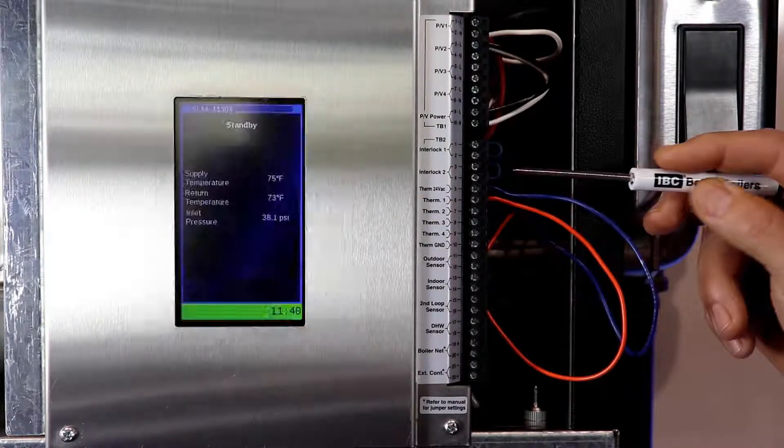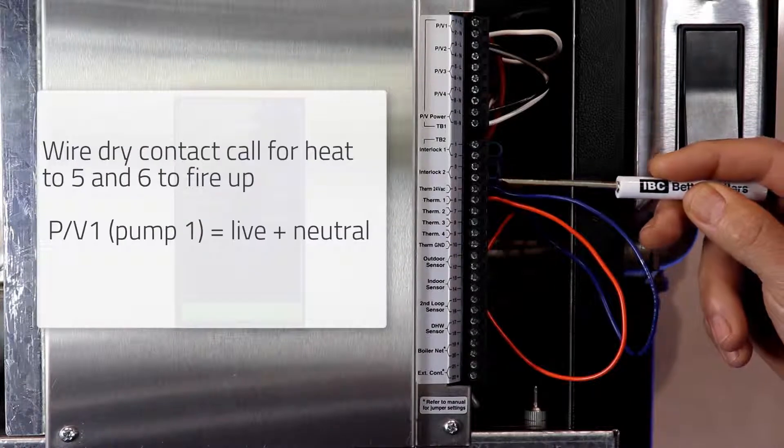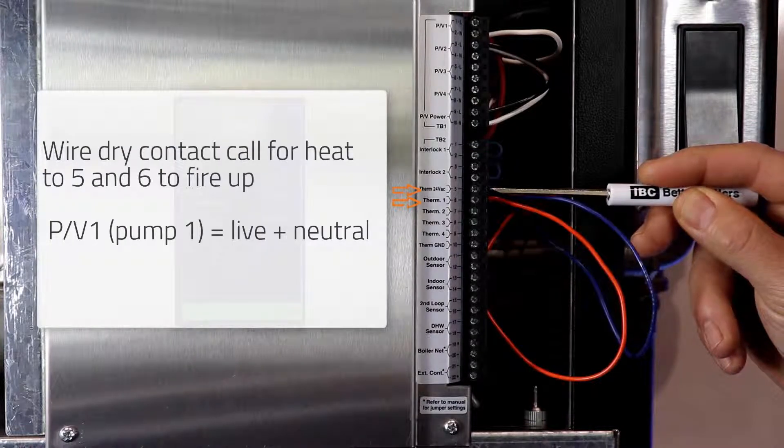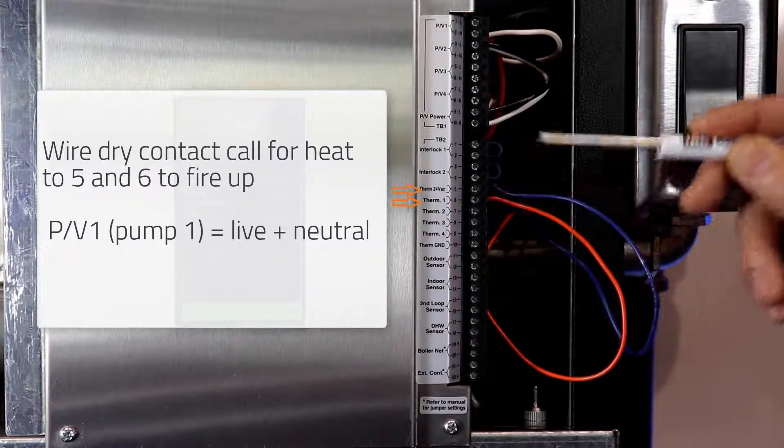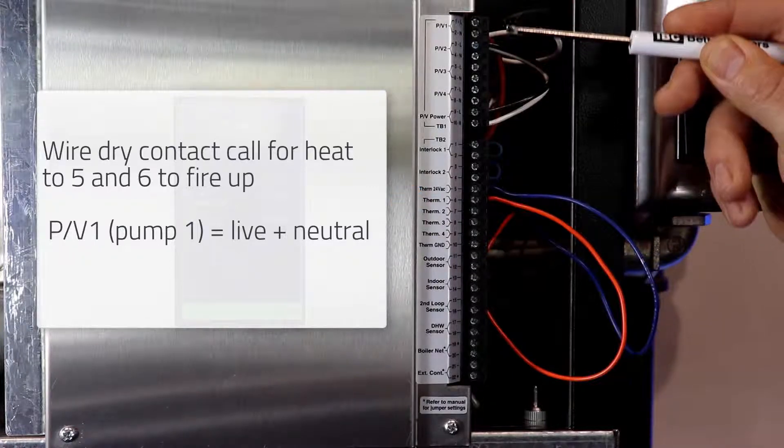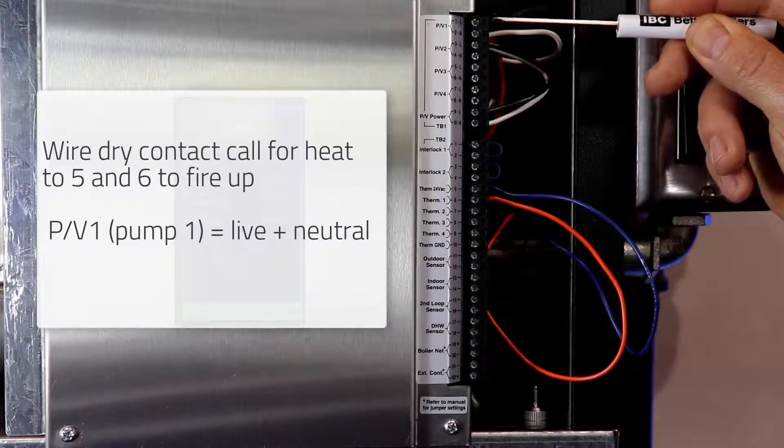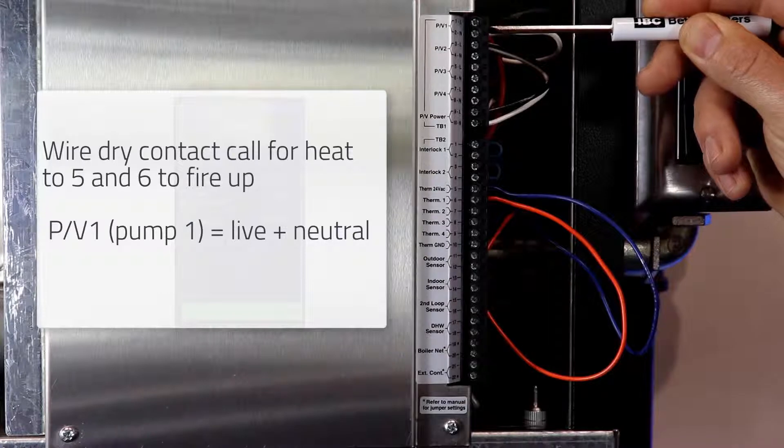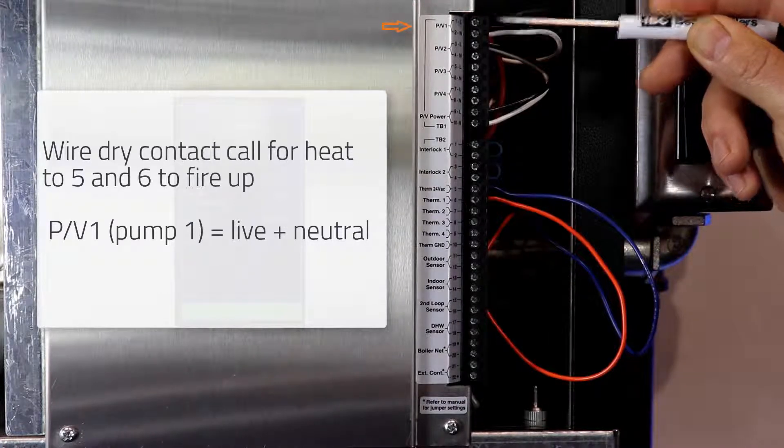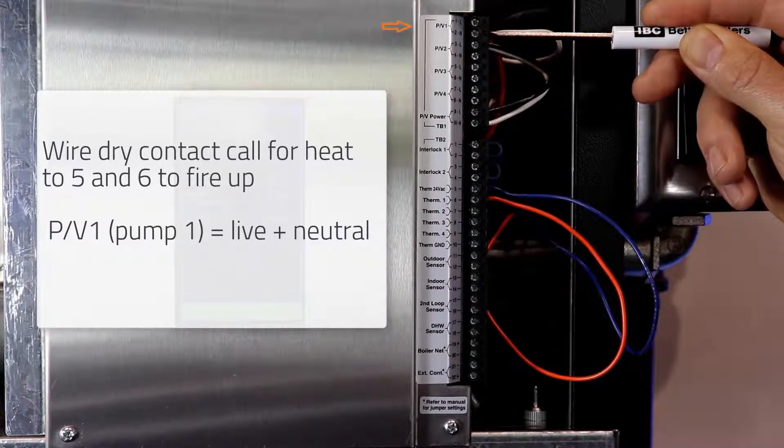Correspondingly, if you wire a dry contact call for heat to number 5 and 6 on term 1, when that dry contact closes, it will energize PV1 or pump number 1 with a live and a neutral for the pump.